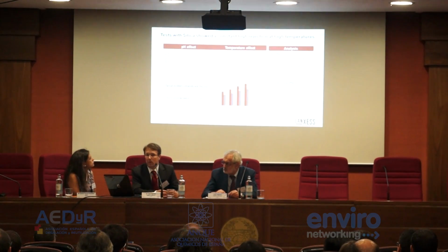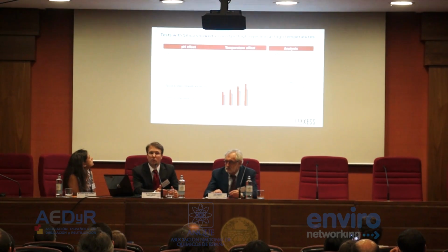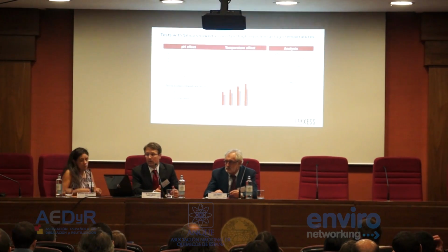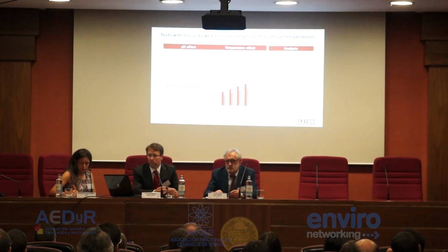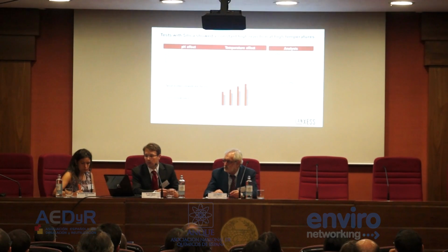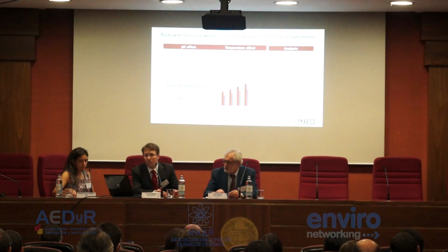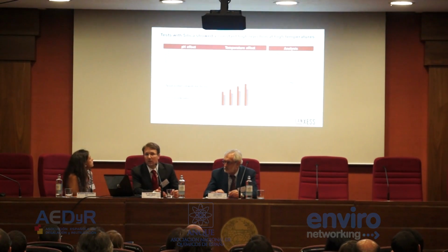Since silica is also very important, especially if you're working with boiler feed water, we also checked it. Here you have two effects. At high pH, you of course have electrostatic interaction, but at low pH we start the polymerization of the silica. Therefore, you also have an increase in rejection here. But you can see the pH effect also showed a higher rejection. The temperature stability is also very high. That is the reason I also added the temperature variant below.